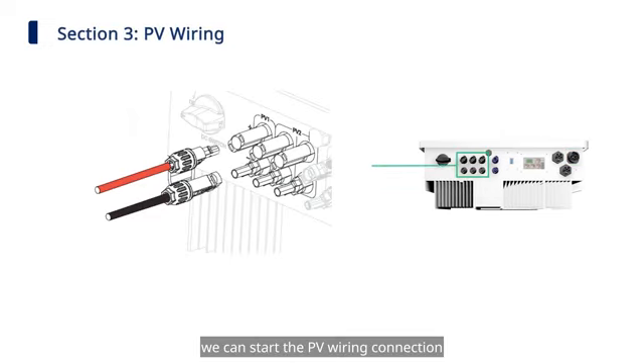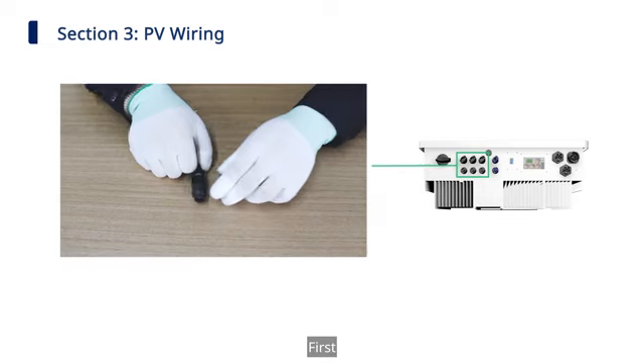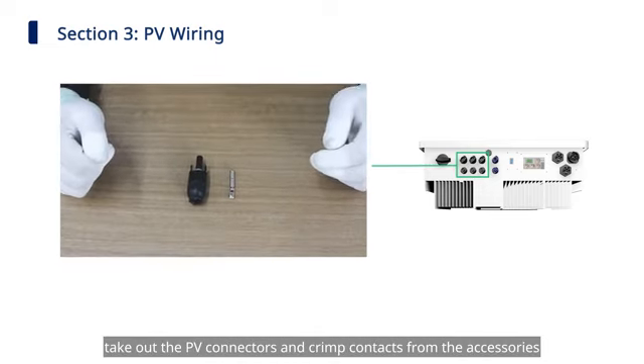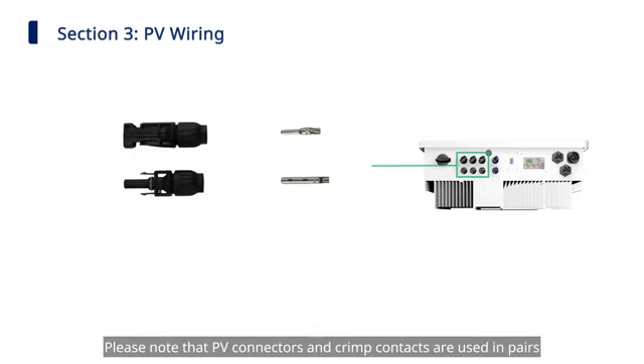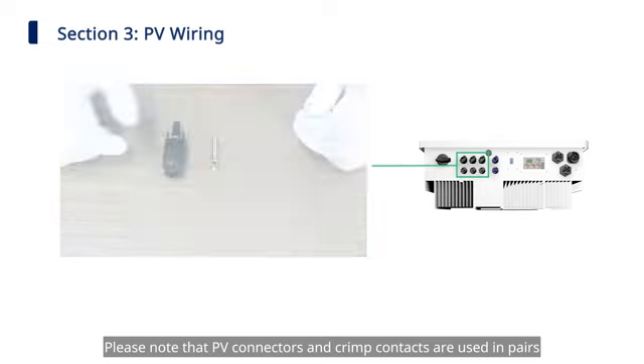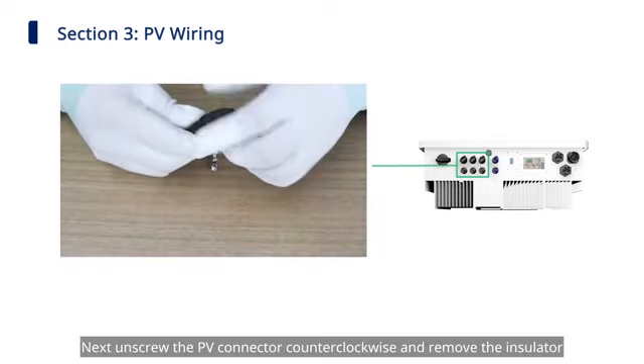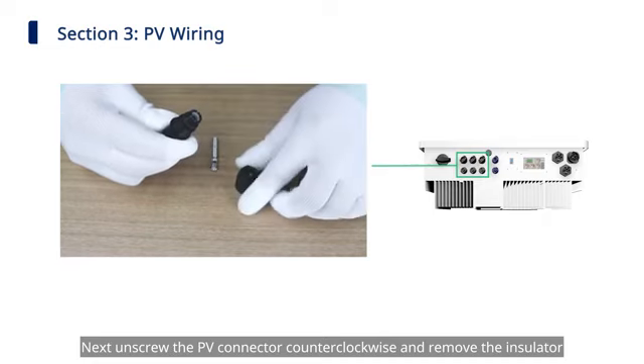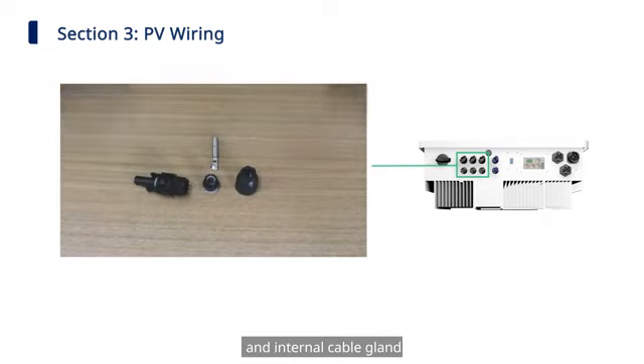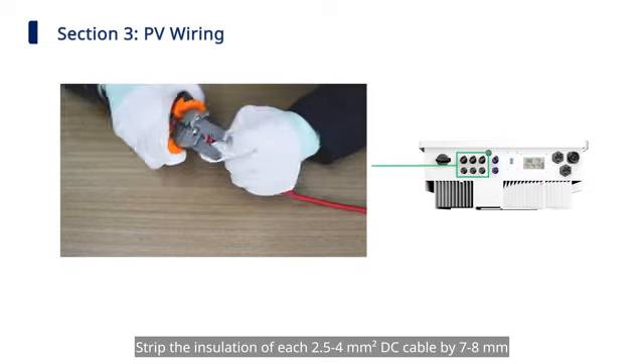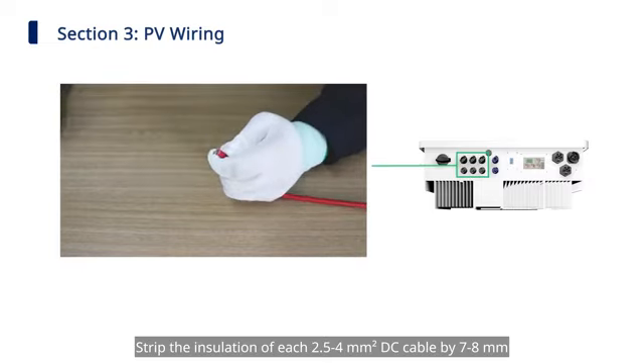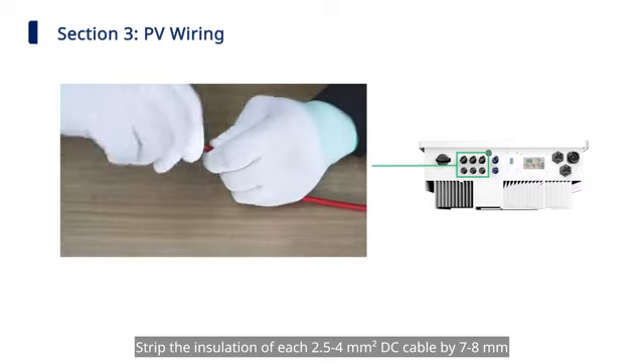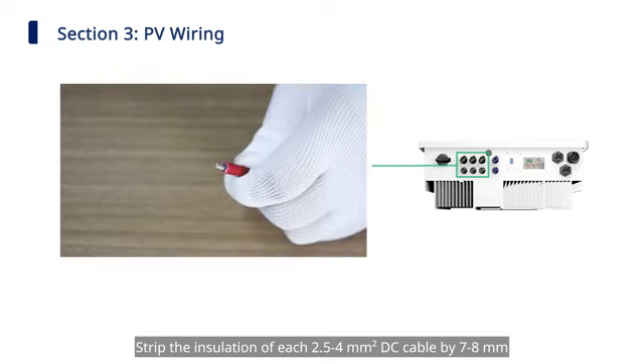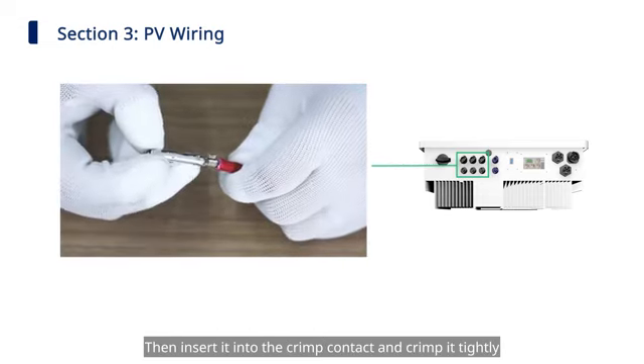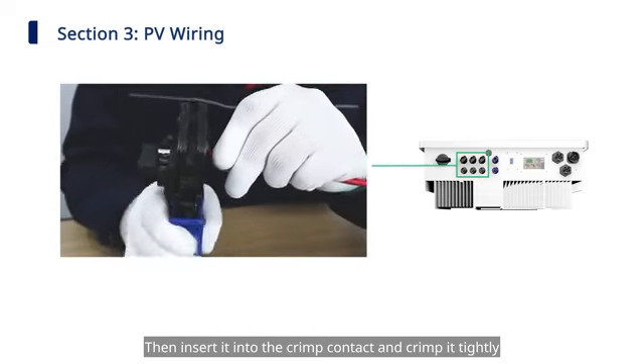Next, we can start the PV wiring connection. First, take out the PV connectors and crimp contacts from the accessories. Please note that PV connectors and crimp contacts are used in pairs. Next, unscrew the PV connector counterclockwise and remove the insulator and internal cable gland. Strip the insulation of each 2.5 to 4 square millimeter DC cable by 7 to 8 millimeter. Then insert it into the crimp contact and crimp it tightly.